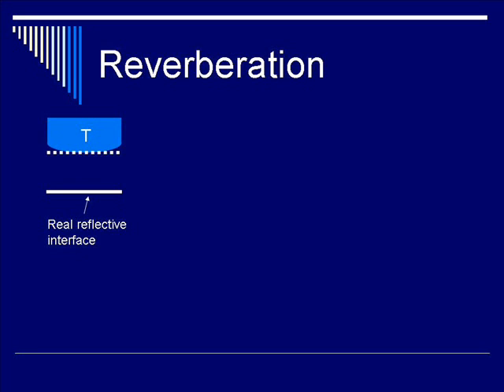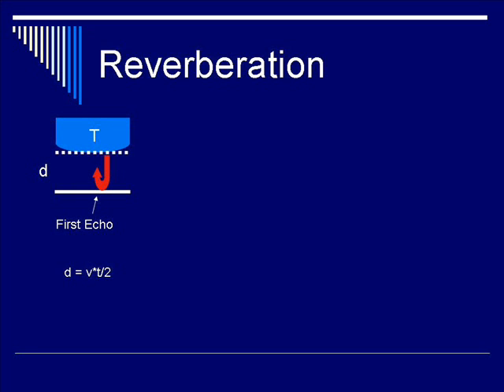In doing so, this reflective echo gives you the signal to form the image on the ultrasound video screen. The red arrow denotes the signal returning from the interface, which is the first echo, and also it is the real image. Distance d from the transducer surface is calculated by the simple equation: velocity times time divided by 2. This is how the ultrasound machine calculates how far to place the image based on the propagation time, assuming a certain velocity of the ultrasound wave.